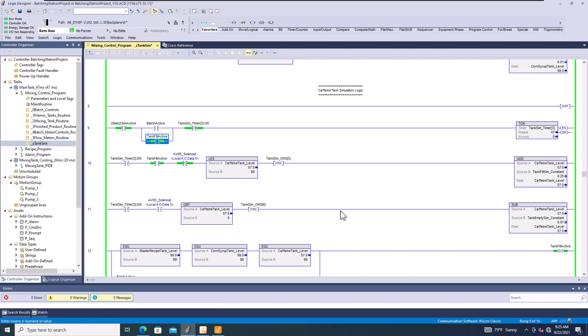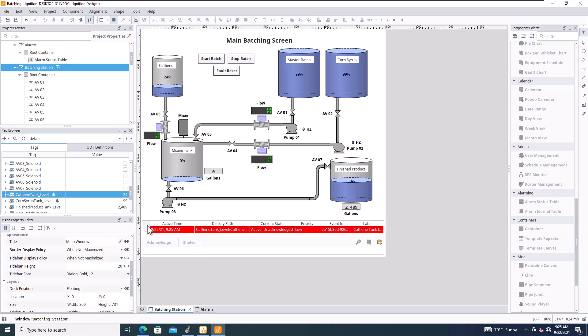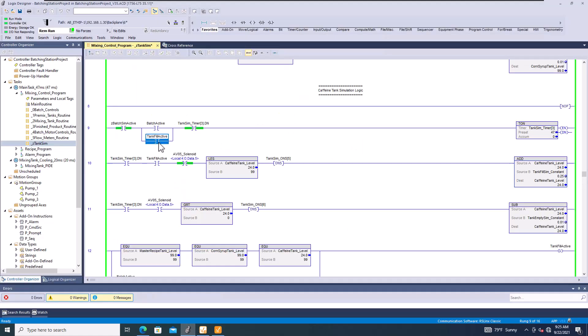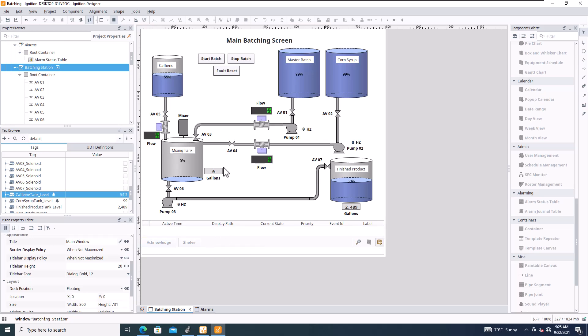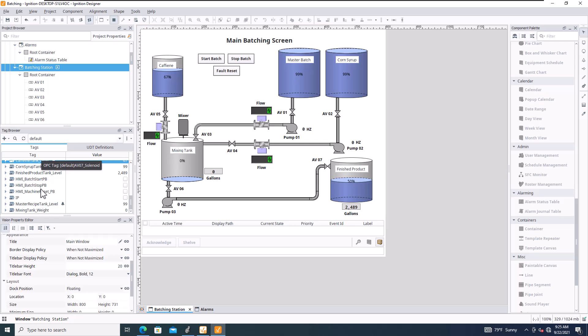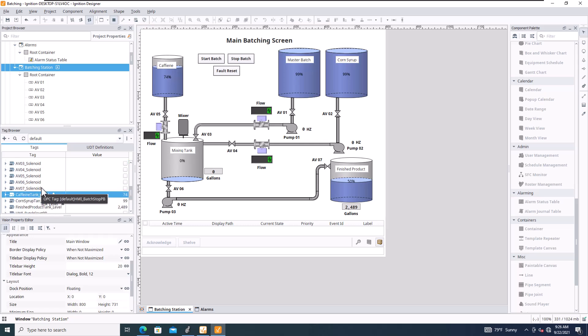Let me demonstrate an unacknowledged alarm. I'll turn off batch fill so the alarm triggers again. This time I'll fill the tank back up without acknowledging first. Once the level is no longer in alarm state, the alarm stays until you click it and hit Acknowledge. That's a simple alarm scheme — you can also add SQL alarm history and much more.